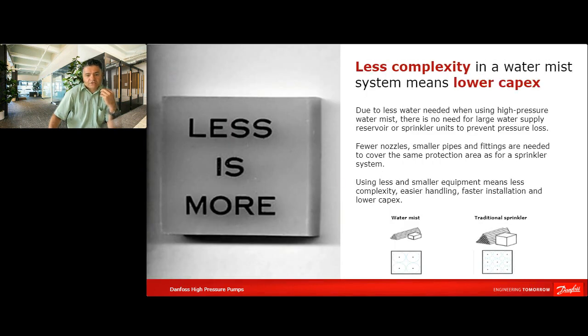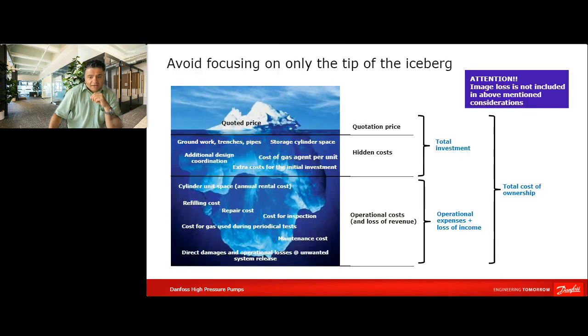And when we talk about the lower capex, as I said, for the same compartment with the same dimensions, you need fewer nozzles in the high pressure water mist, and as a result fewer pipes and less material and lower installation costs compared to a sprinkler system. And this saves a lot of money on the capex side. And then I come to my last slide.